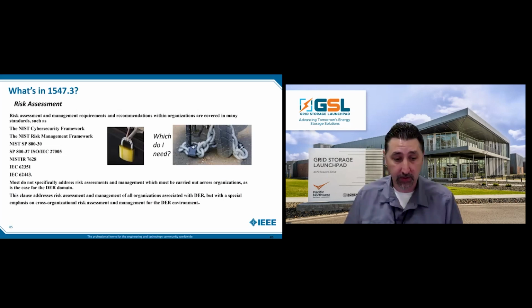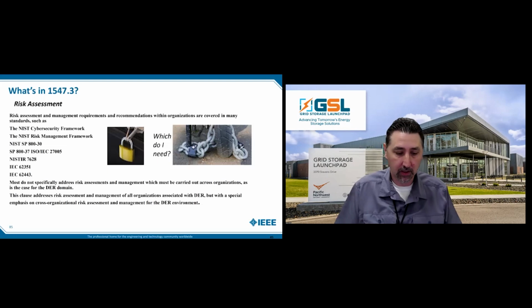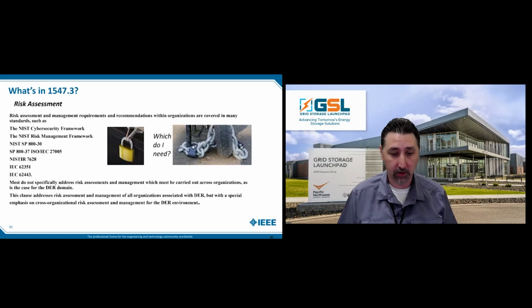So there's this risk assessment in there, and a lot of 1547.3 in general, there's a lot of documents out there, but it puts all of these key best practices into one place. It's always going to tell you to look through the biblio and make sure you're looking at other documents like the cybersecurity framework, risk management framework, and so on. All of these standards have some risk assessments associated with them. Since it's not a formal standard, it's a guide, you're not going to get a defined process for exactly how you do it. You're going to get guidance. This is really important to look at both .3 and the risk assessments they've identified, but also in your jurisdiction, whether you're running operations at the utility or you're an aggregator, you're definitely going to have unique things you need to assess risk at.